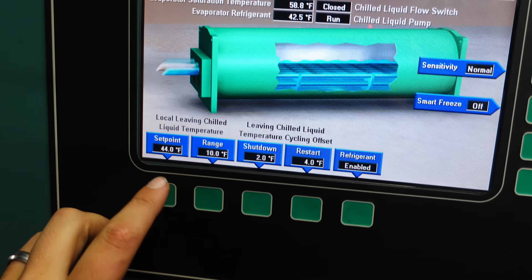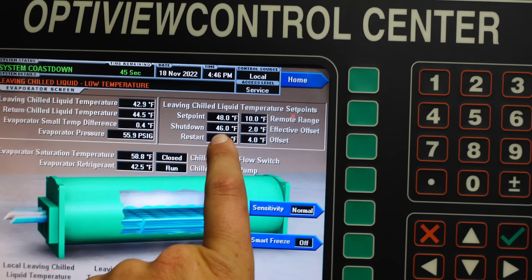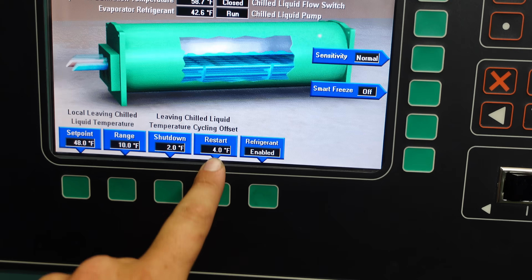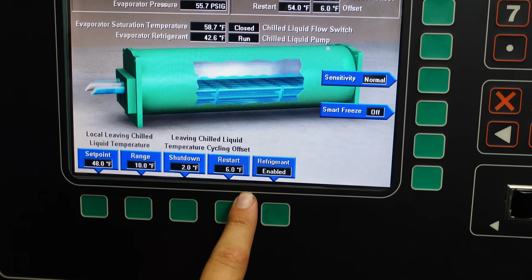What we are going to do is, it is fairly cold out. We're gonna run this at a 48 degree set point, and this will help us maintain a more stable building. So we're going to shut down at 46. We're going to restart at 52. All right, so 4 degrees. I'm going to turn that 4 into 6. So 6 degrees restart, shut down 2 degrees.